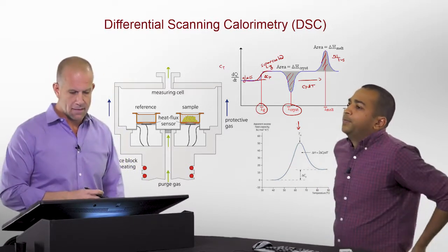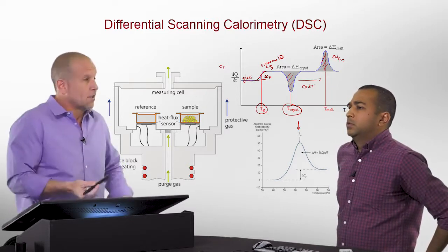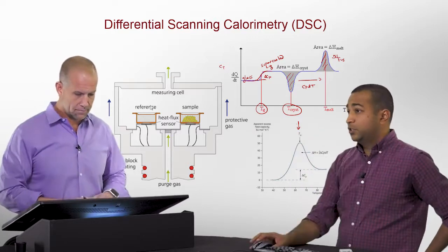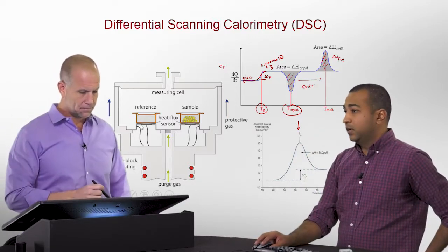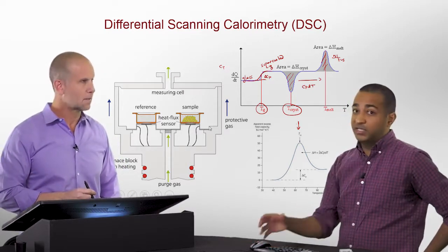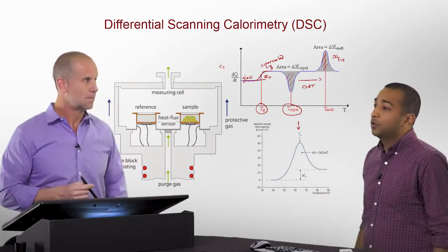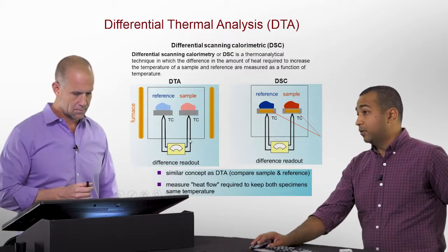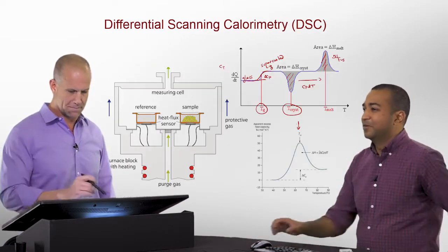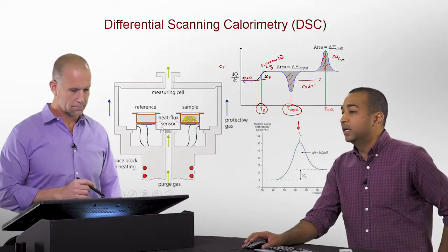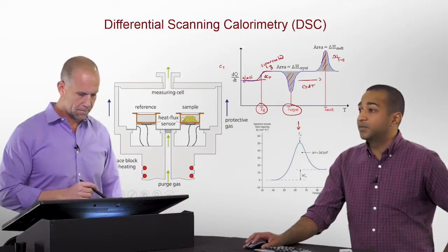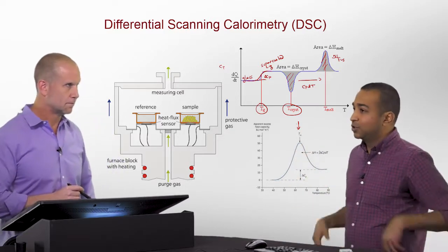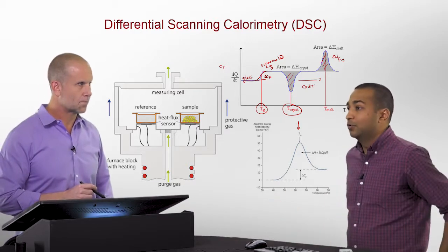Really, the main measurement in DSC is thermocouples. In most modern DSCs, a big metal plate — which is inherently one of the thermocouple materials — provides good thermal conductivity for both the reference and sample. They directly attach the other metal, providing thermocouple probes directly under the sample and reference pans. That's why this technique ends up giving you incredible resolution and sensitivity.